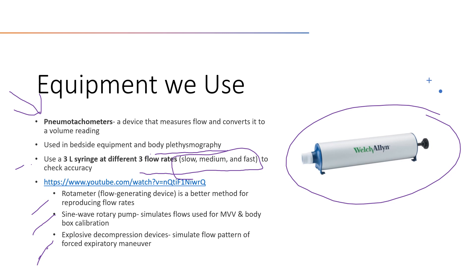It is required that PFT equipment is calibrated before performing any tests for that day. If you show up to the PFT lab, you'll see the pulmonary function technologist or respiratory therapist calibrate the machine at the start of the day. That calibration is recorded to demonstrate accuracy for all patients seen afterward. If it was calibrated yesterday, that doesn't count — it must be calibrated for today.